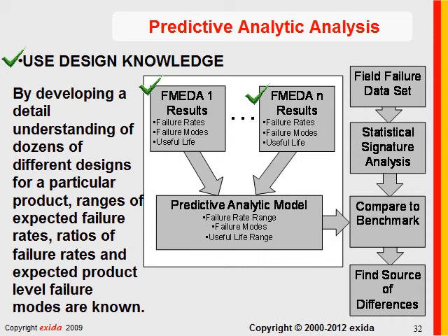FMEDA data is an excellent choice for the initial design. We just did a webinar on FMEDA data, and we do explain in that webinar that, in fact, FMEDA data is product specific, not site specific, so it doesn't include maintenance failures.